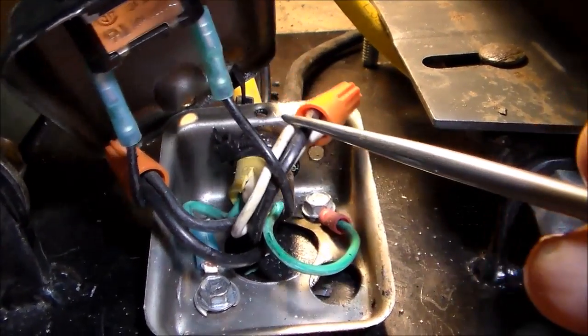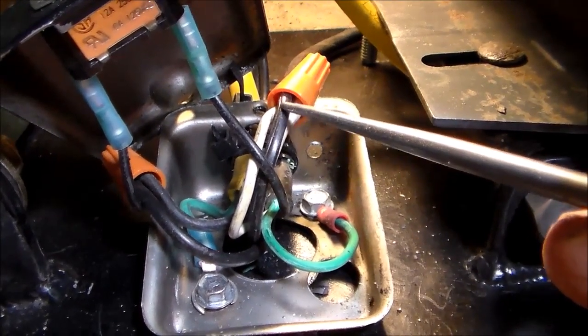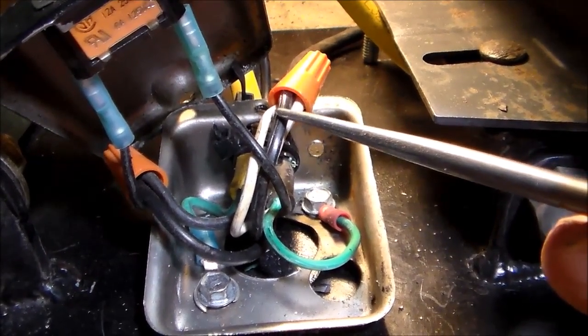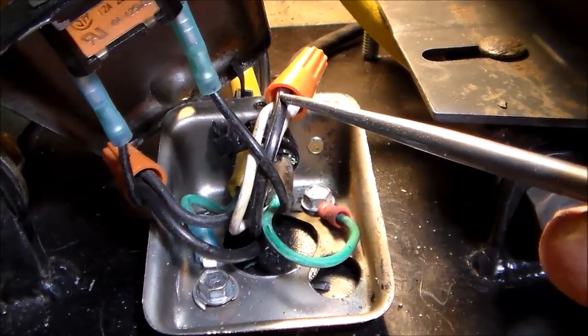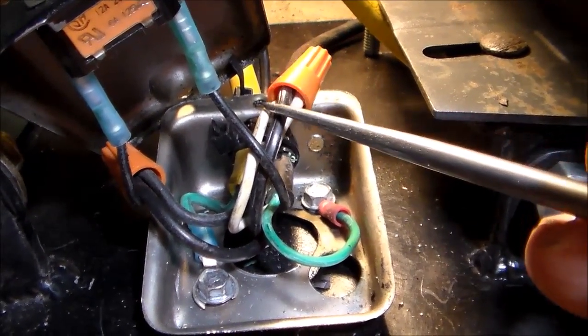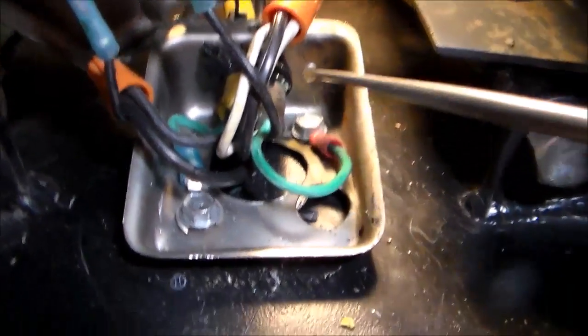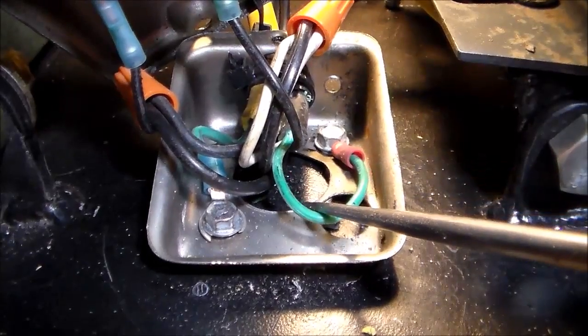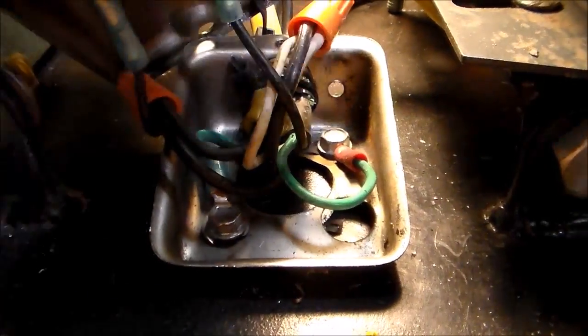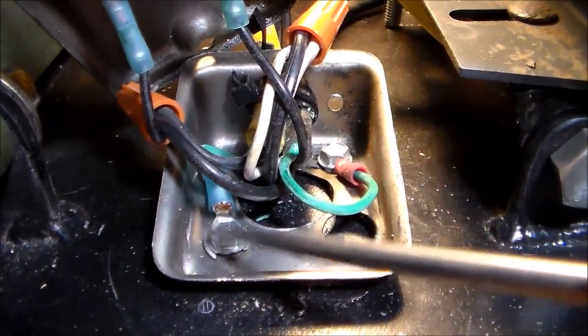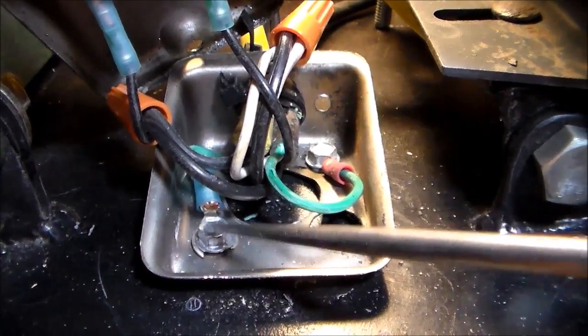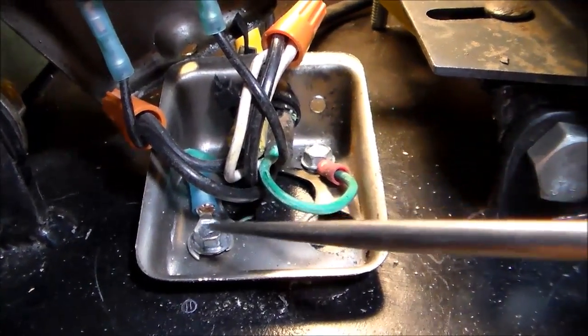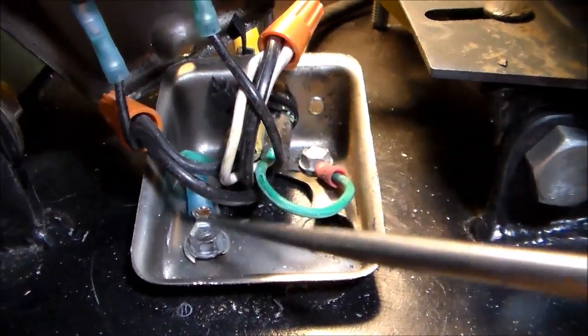And simply, all you do is take all your neutral conductors right here. The way you know the neutral conductor on a lamp cord is there'll be ridges on the side of it. It's marked. It's different than the, if you ever look at it close, they're different than each other. Take all three of your neutrals, the power, the lamp, and the drive. Wire nut those together. Land your grounds from the power coming in and back in here. I've got the other one. That's the ground that goes up to the drive. And, of course, they're grounded to the base. So everything, the motor, drive saw, everything's all grounded together. Don't leave the grounds off. That is where you can get hurt.